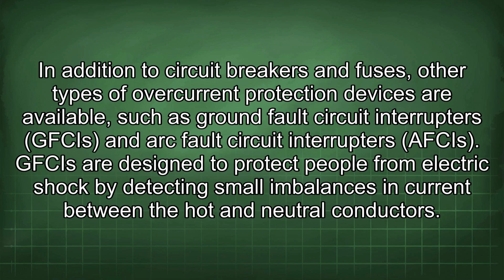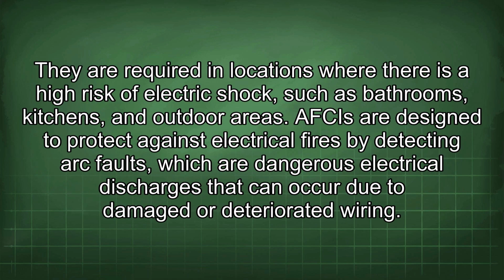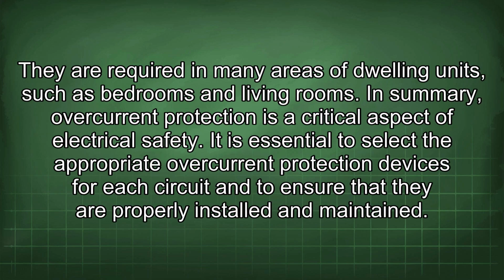GFCIs are designed to protect people from electric shock by detecting small imbalances in current between the hot and neutral conductors. They are required in locations where there is a high risk of electric shock, such as bathrooms, kitchens, and outdoor areas. AFCIs are designed to protect against electrical fires by detecting arc faults, which are dangerous electrical discharges that can occur due to damaged or deteriorated wiring. They are required in many areas of dwelling units, such as bedrooms and living rooms.